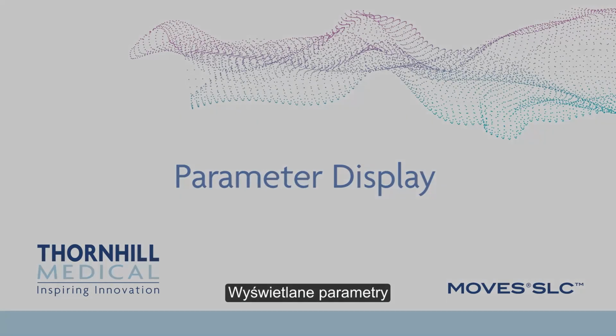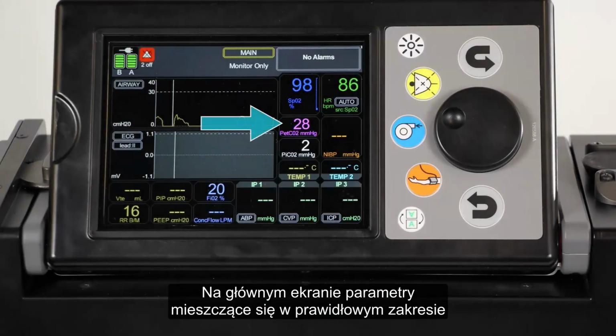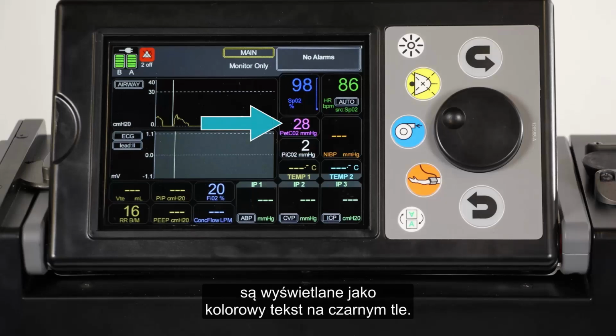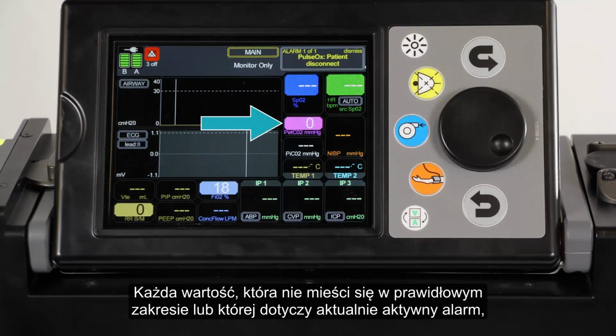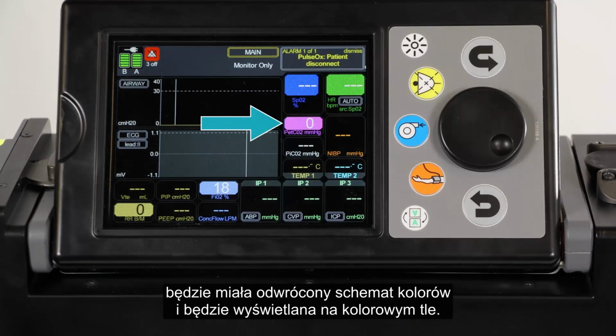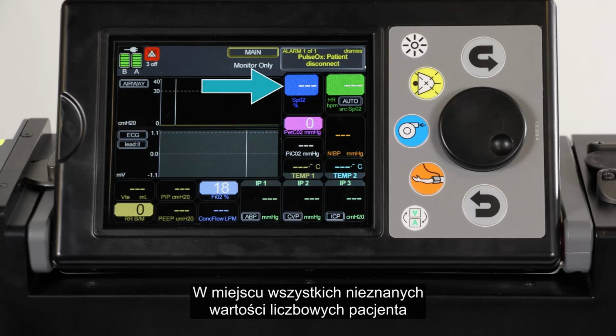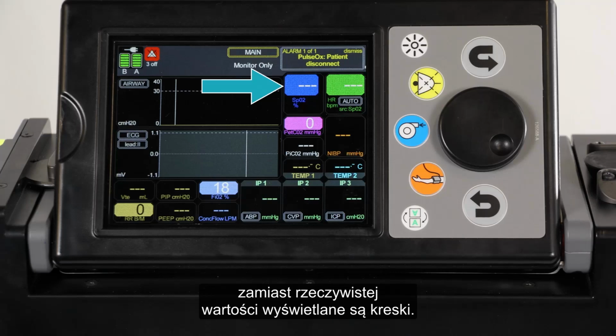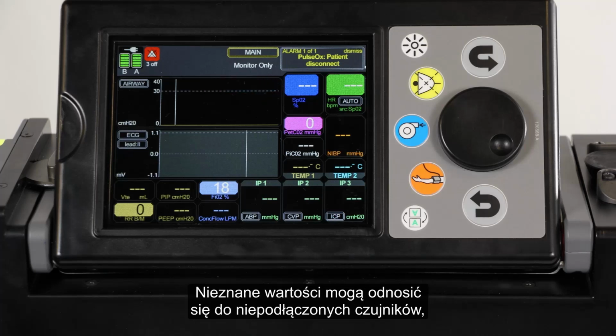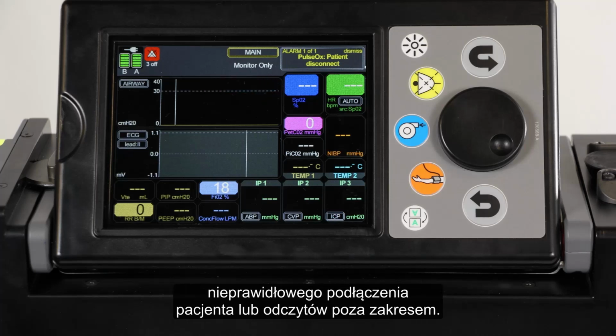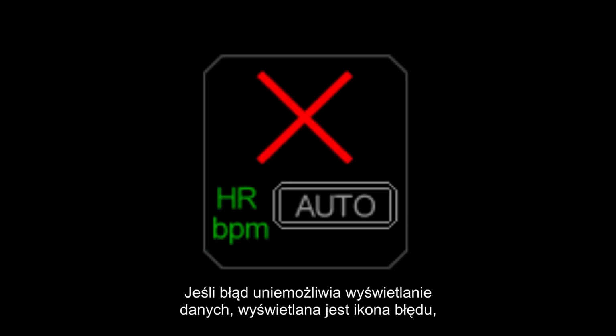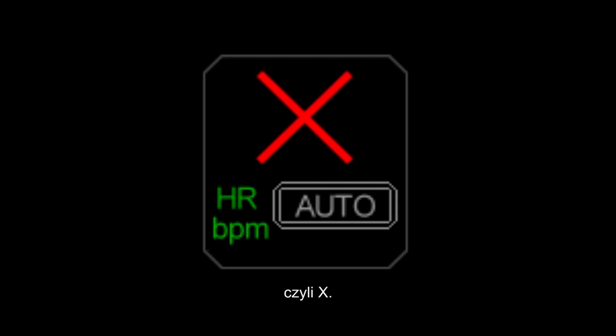Parameter display. On the main screen, parameters in the normal range will be displayed as color text on a black background. Any value that is out of normal range or has an alarm currently active will have a reverse color scheme with the background displayed in color. Any unknown numerical patient values have a default display of dashes instead of an actual value. Unknown values may relate to sensors having not been connected, improper patient connections, or out-of-range readings. If a fault prevents data display, the fault icon, which is an X, is displayed.